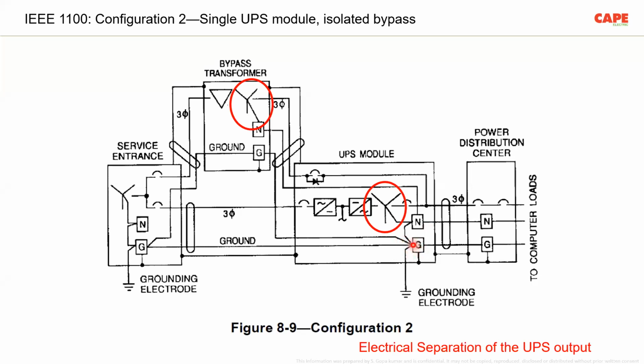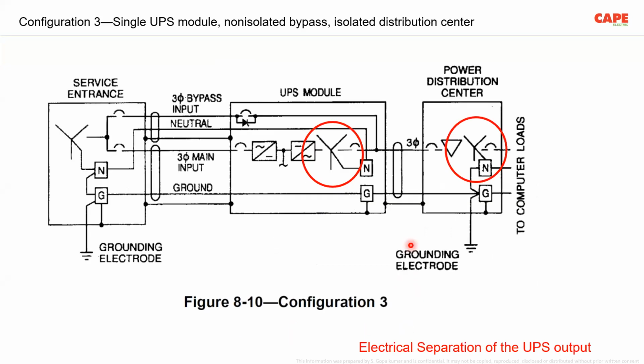Please understand. Now, the grounding terminal or the earth terminal is further connected. That is a different case. This has nothing to do with the neutral. This has a common equipotential bonding. But where you connect the neutral is the earth terminal. I am showing another configuration. There are 8 configurations shown in IEEE 1100.